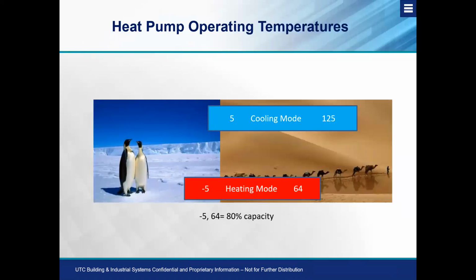Now, let's look at operating temperatures as far as the heat pumps are concerned. In the cooling mode, we'll range from 5 degrees all the way up to 125 degrees. And at that 5 degrees, we're going to give you 80% of that system's nominally rated capacity. Okay. And in the heating mode, we can go all the way down to -5, all the way up to 64 degrees. And again, at that -5, we're going to give you 80% of the rated capacity.